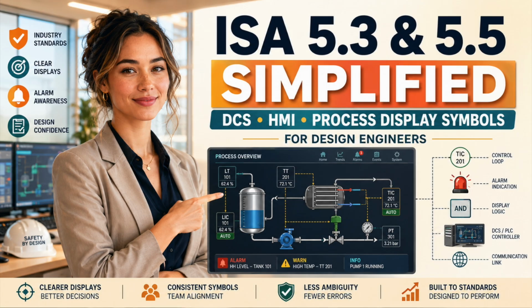The operator needs to know what is running, what is stopped, what is available, what is abnormal, where material is flowing, which variable is approaching a limit, which controller is responding, which path is blocked, and whether the displayed information can be trusted. Maximum information does not create maximum understanding. It often creates engineering camouflage, where everything is visible but nothing is prominent.